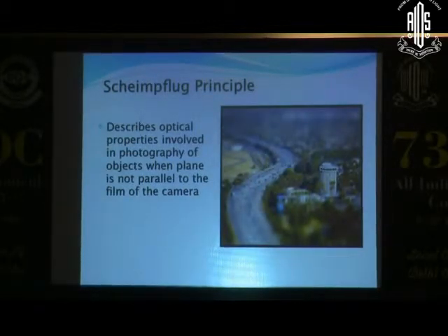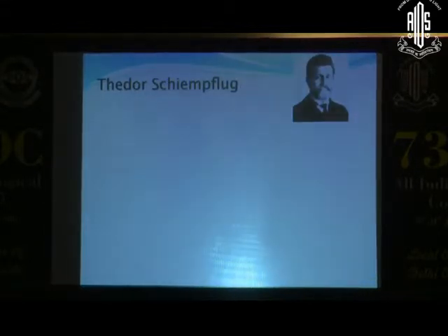So what exactly is the principle behind the Pentacam? This is exactly the Scheimpflug principle. It describes the optical properties involved in photography of objects when the plane is not parallel to the film of the camera. So normally when the plane is parallel to the film, when you take a photograph, the entire image is very crisp and clear. But when you're imaging a landscape and you take a photograph, the objects beyond and within that focal distance will be blurred. So it's very important when you're actually devising such an instrument that the image is crystal clear.